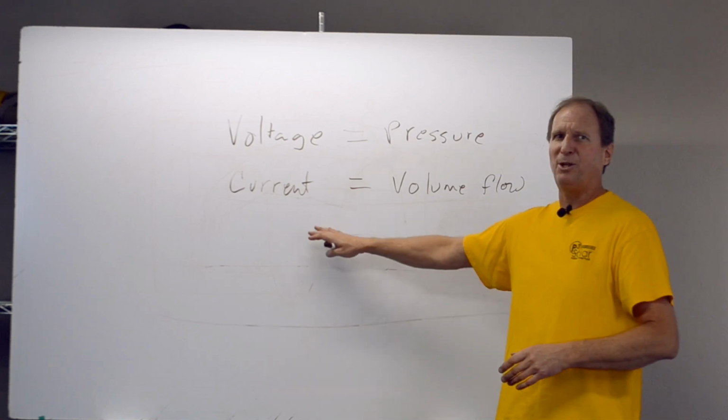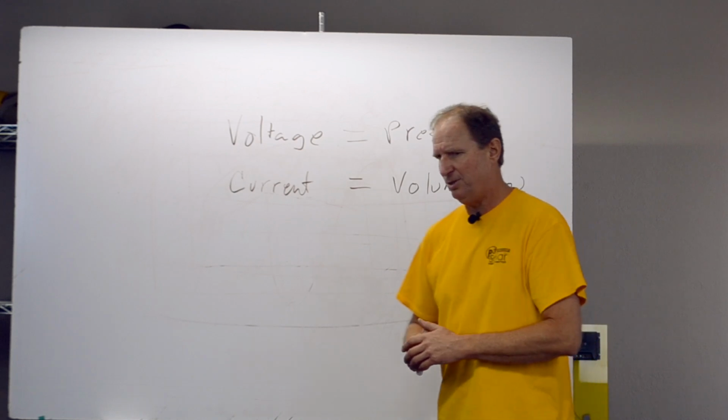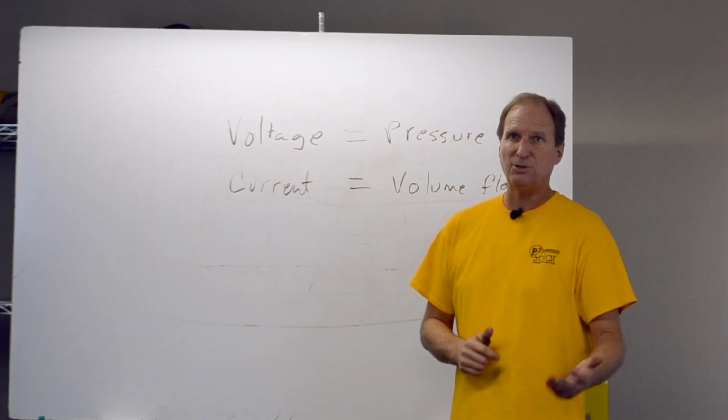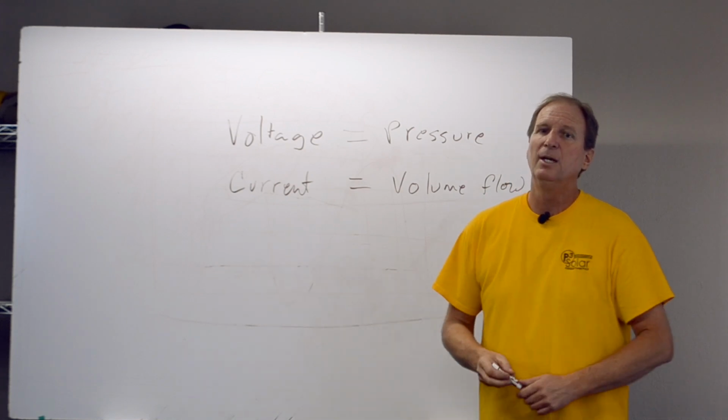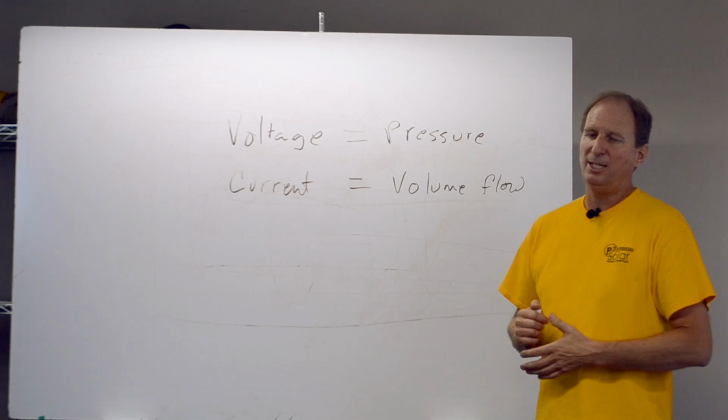So you don't want to get anywhere close to the maximum current rating of the wire size you choose to use in your cart. For the most part, we're swinging around 7 amps off the charge controller, but the motor itself takes 25 to 30 amps. So you want to have wire size big enough to handle that.